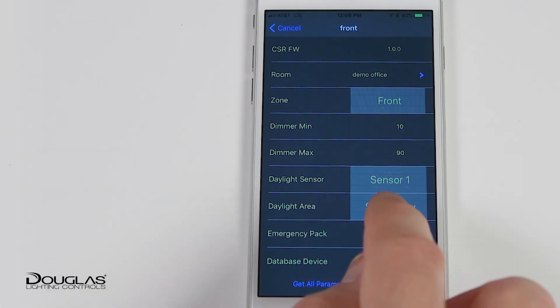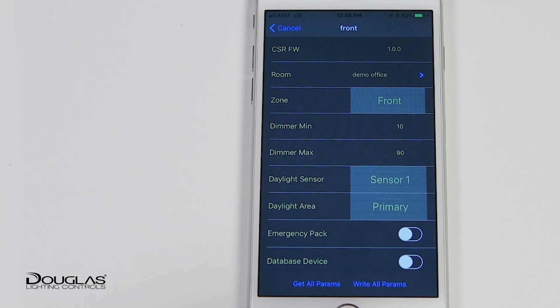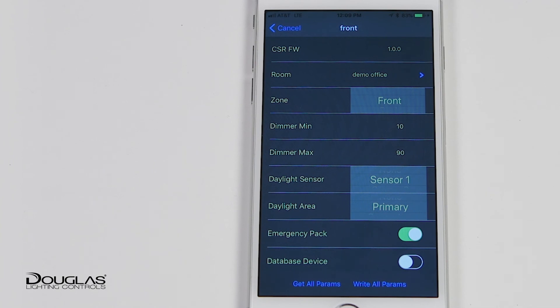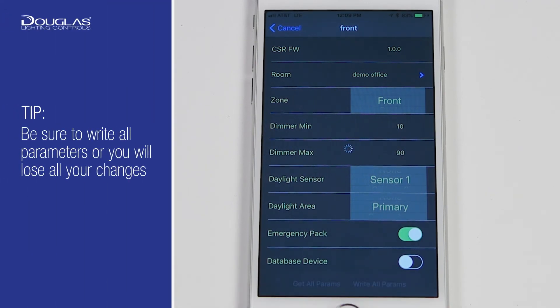Daylight sensor defines which, if any, daylight sensor the controller will be controlled by for daylight harvesting. Primary or secondary daylight area can be selected. Unique to Douglas Lighting Control's Bluetooth system is the ability to control emergency lights through the UL924 listed controller. By providing a backup power source to the controller and identifying the controller as to be used for emergency light, the controller will be actioned on at 100% if there is a power failure. Lastly, be sure to write all parameters to save the settings before leaving this page.